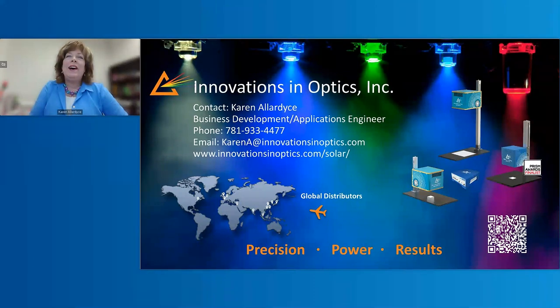So can it independently bias the top and bottom of perovskite? Yes, absolutely. It is in fact a key feature of the LumiSuns. We use a multi-channel LED array with individually controllable wavelengths, and that's really key, each with high uniformity and capable of a range anywhere from 0.1 suns all the way up to 1.2 suns. So you can actually go greater than 1 sun. Gives you a little bit of margin in there.